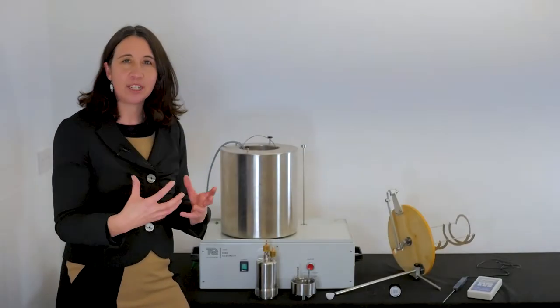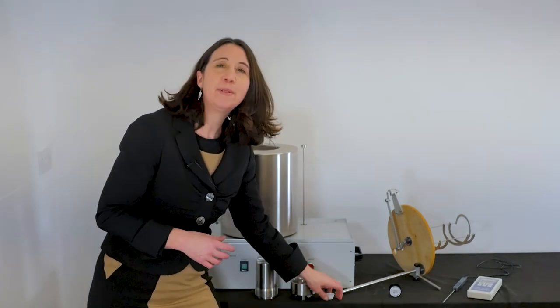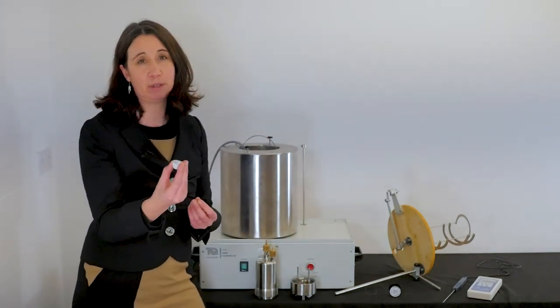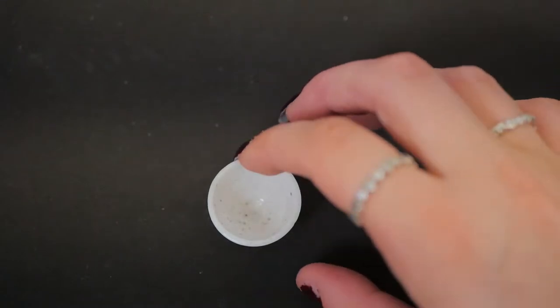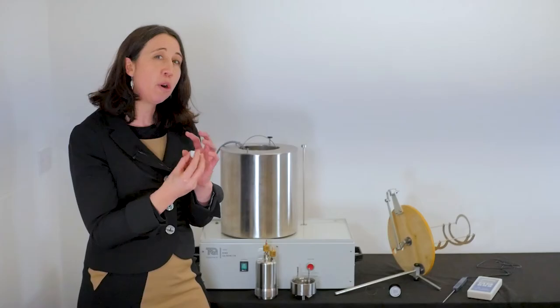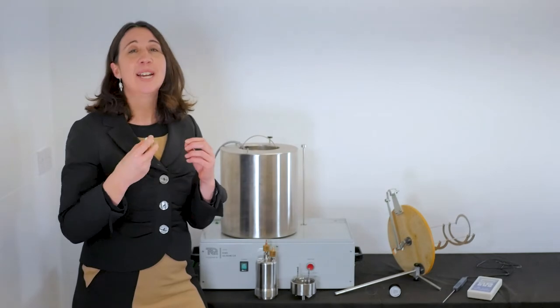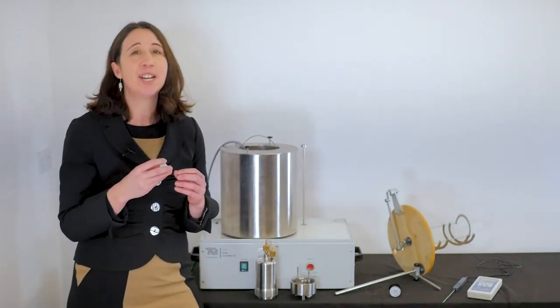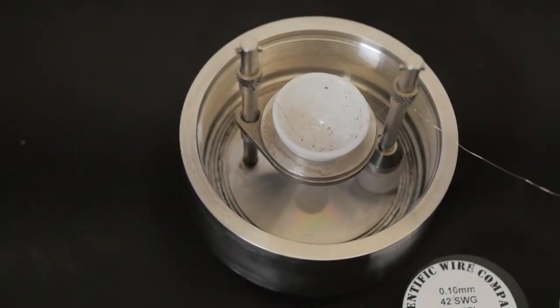Now to the heart of the apparatus. The crucible here is made from Vitreosil and is loaded with a precise amount of fuel. Ignition wire is fitted across the fuel to make contact and is passed through the slots in the terminals and locks into place with this sliding nut.